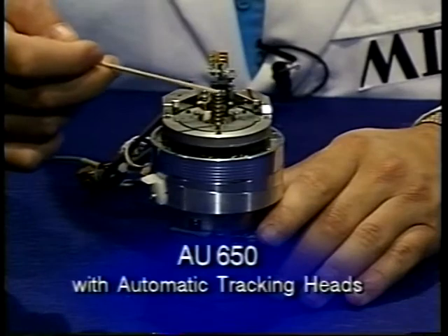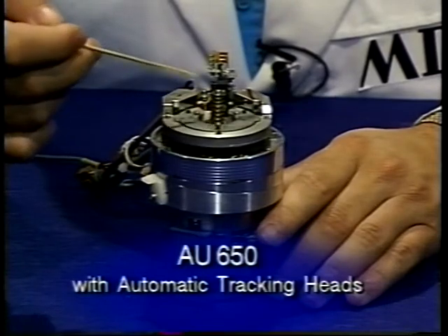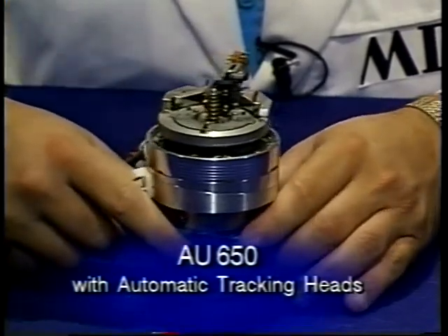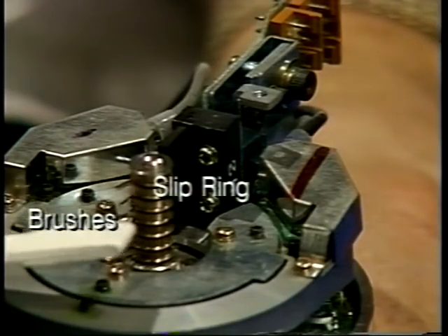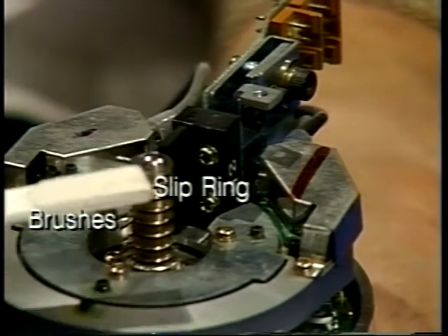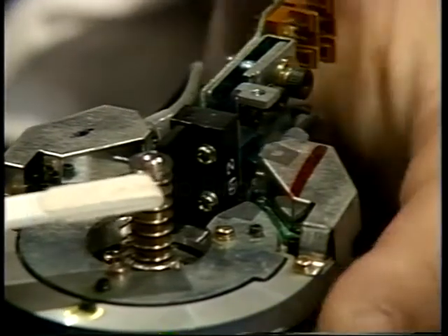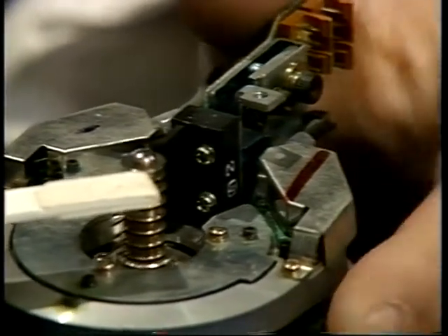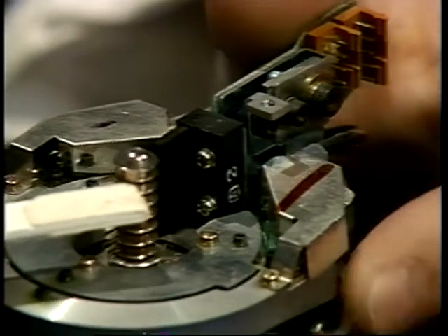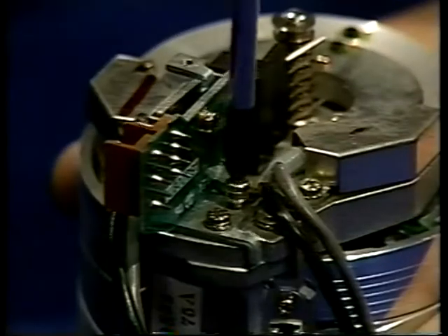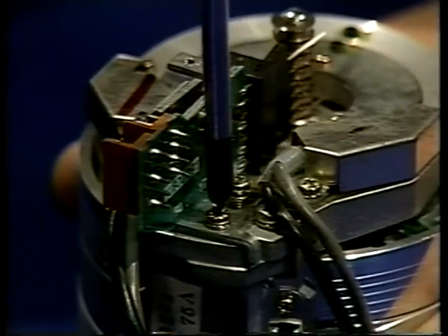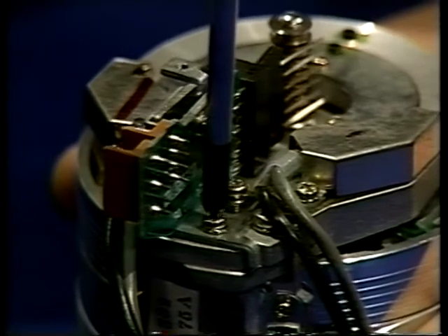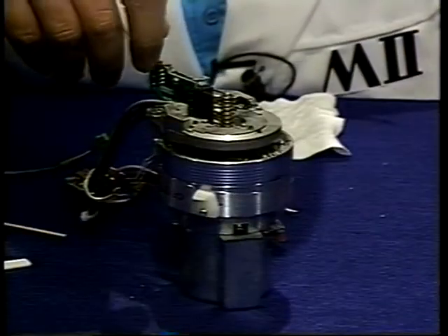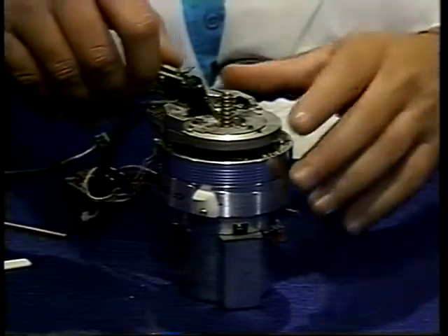This is an upper brush assembly from an AU650, a unit that has automatic tracking heads. The slip ring assembly is in the front, and the brushes are on the side. Using a cleaning stick, clean inside each one of the slip rings while turning the assembly. To disassemble the brush assembly for cleaning, remove these two screws. And then remove the brush assembly.